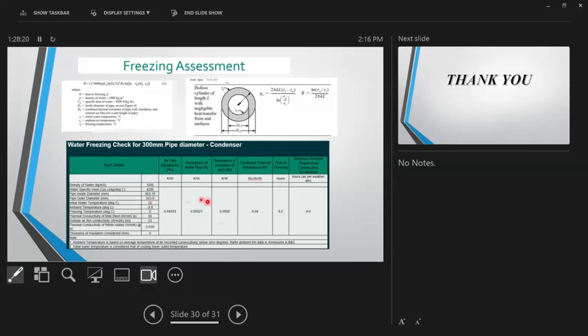Okay. Now, based on the AECOM weather bin data, you just see for how many hours continuously the temperature was below 0 degrees centigrade. Now, in this particular case, the minimum ambient temperature, below 0 degrees centigrade, was for 9 hours continuously. This pipe takes 9.2 hours to freeze. Of course, these are too close conditions, too close to be comfortable. So we provided insulation to this.